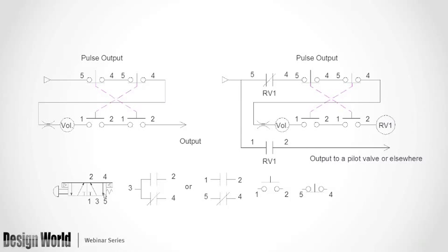So the air comes through here. Comes through a little bit of a flow control. This is a restrictor. Now, this could be an adjustable needle valve, or it can be a fixed orifice. When we put a fixed orifice in there, it keeps the people with knobitis away from making adjustments. Makes it a little bit harder for them to do that because the orifice is a fixed amount of air that will go through it, especially when I have a fixed amount of air going into this volume chamber.